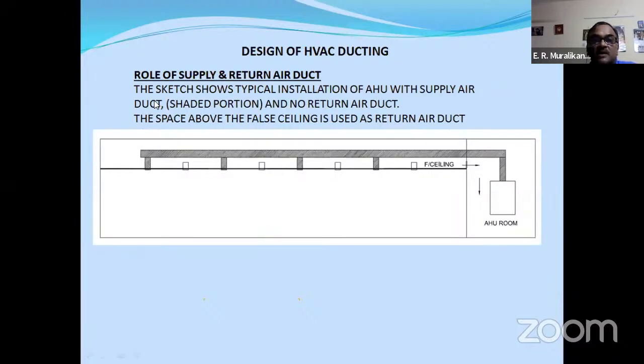See, here is the typical installation. Here is the AHU room. You are having a supply duct and a return duct. What will happen here is the space above the false ceiling, although considered as a return plenum, is not considered in the heat load. Very important. We generally calculate the heat load up to the false ceiling only, and the space above the false ceiling is generally not taken into consideration.